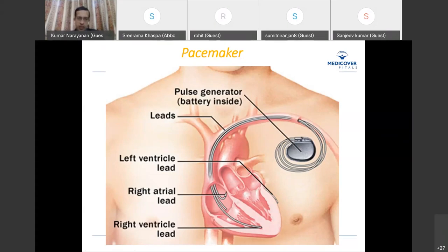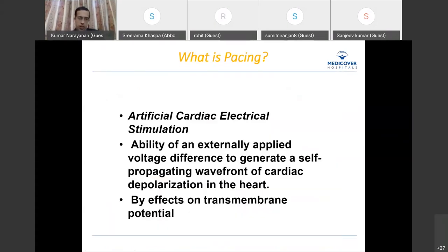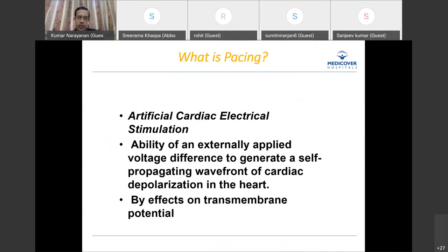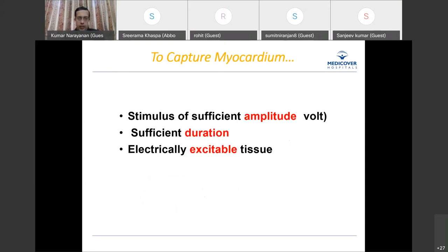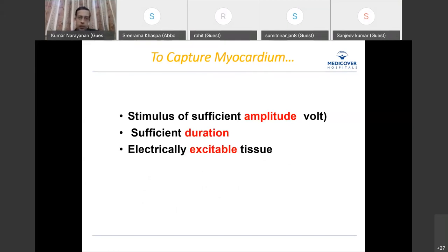The pacemaker depends on the leads both to get information and to convey information to the myocardium. The two essential functions any pacemaker has to perform are pacing and sensing. Pacing is nothing but artificial cardiac electrical stimulation — applying an external electrical signal to generate a self-propagating cardiac depolarization, achieved through effects on the transmembrane potential.